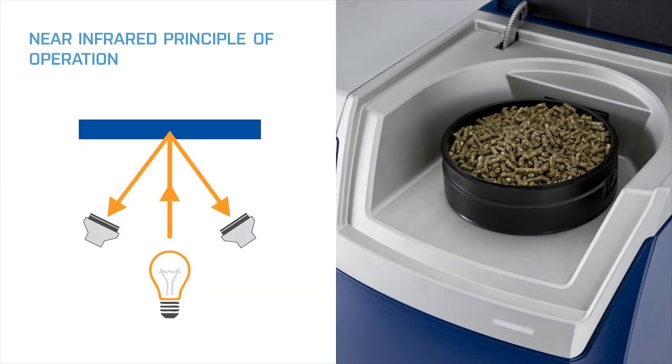Practically what this means in the case of our DS2500 near-infrared system we typically analyze solids using a sample cup as shown in this picture and this cup can receive either ground or unground materials.